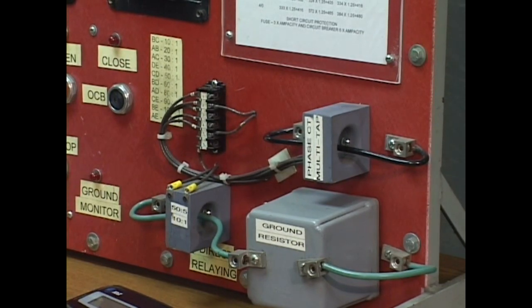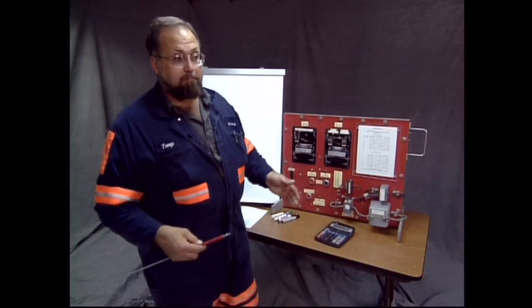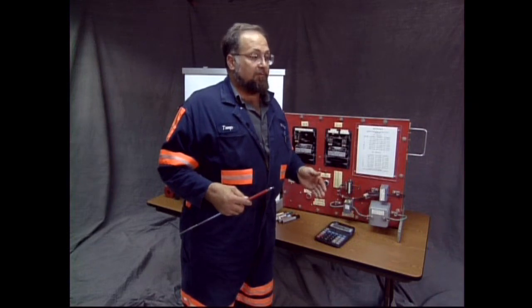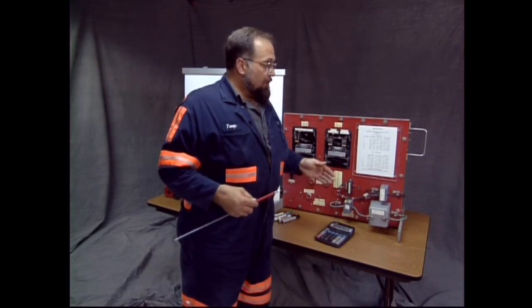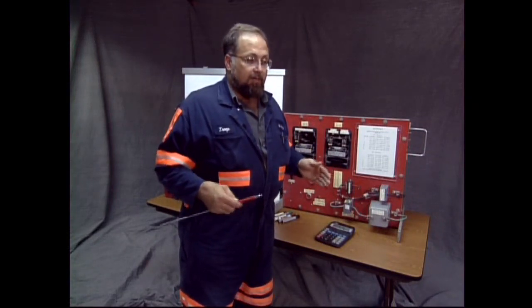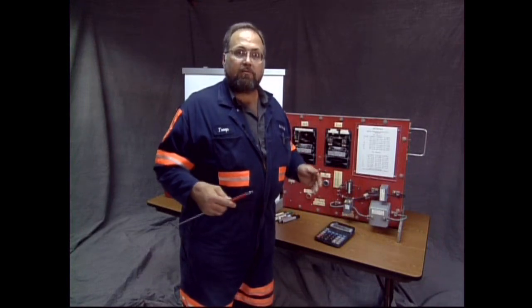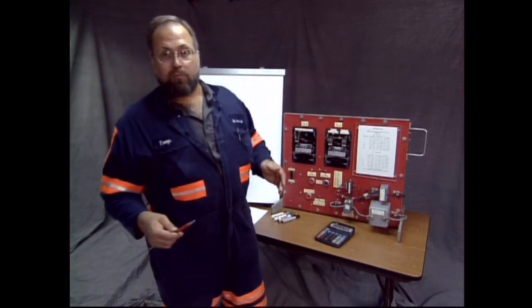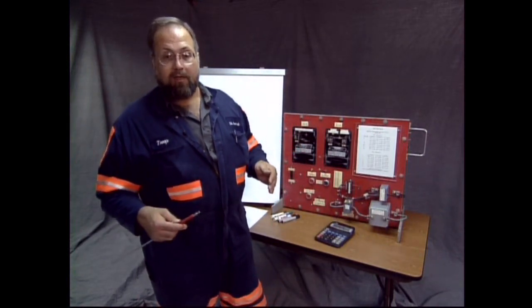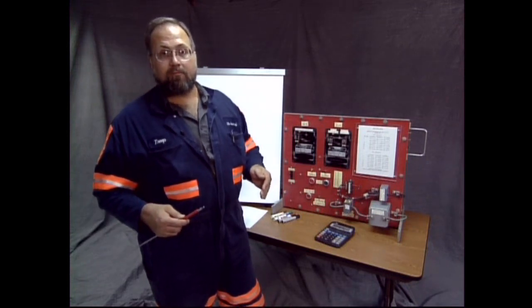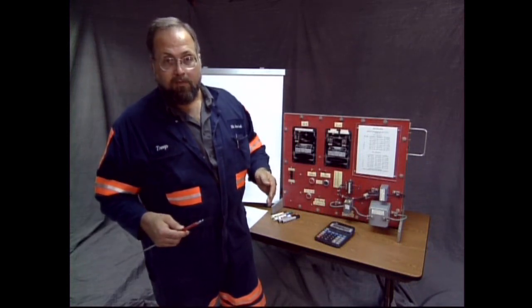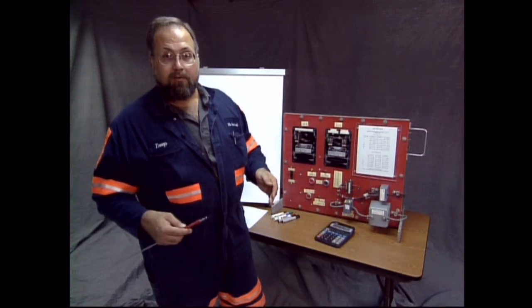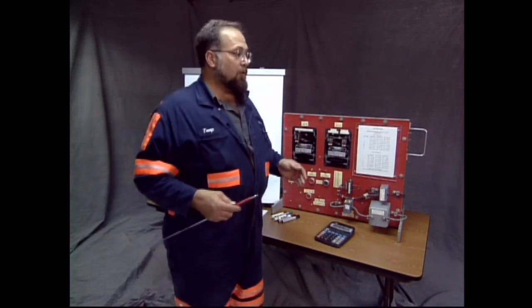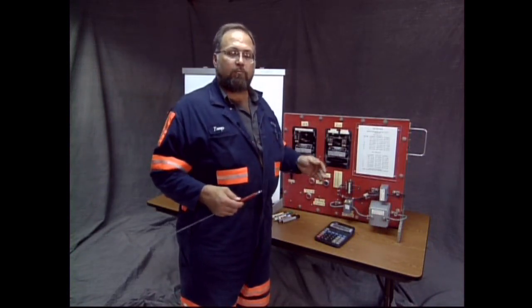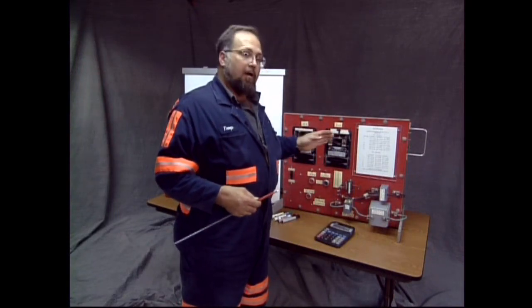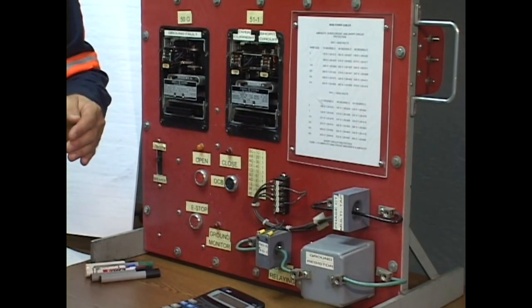Now, it'll carry more current than that. It won't burn up and explode if you put more than 5 amps on it. But if you routinely and sustain a greater ampacity than it's rated for, then it may not respond in a linear fashion. It may saturate the CT. It's saturated with magnetism, and it may not respond correctly as you need it to. So we're going to limit all of our settings to a maximum tap setting of 5 on our overcurrent settings.